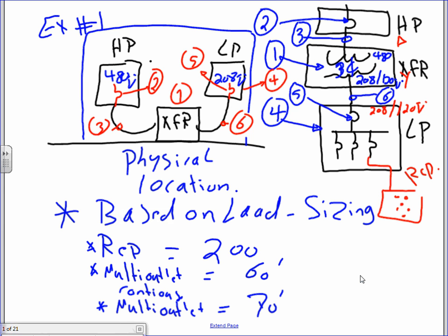Number 4 is the actual panel, the cover or the aluminum inside the panel. Number 5 is the overcurrent protection device inside the panel. Most of the time they're the same, but they don't have to be. So the panel itself, the overcurrent protection device. And number 6, guys, is the secondary feeder of the transformer or the main feeder of the receptacle panel. Can I get you guys to understand this one before you leave? Because every project that you walk in is going to have a combo of this. Every project. You know? Cool? Everybody understand what we have?